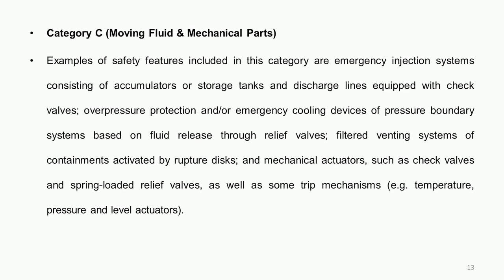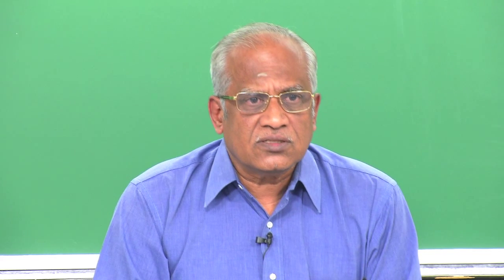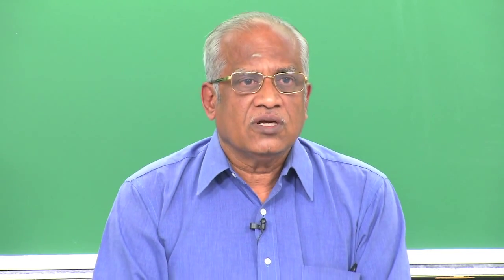In Category C, mechanical parts and moving fluid are involved. Examples are emergency injection systems with accumulators or storage tanks provided with check valves and over-pressure protection, and emergency cooling devices of the pressure boundary systems where the fluid goes through relief valves — such as a spring-loaded relief valve or a pressure-operated relief valve that opens when pressure rises and closes when it comes down.